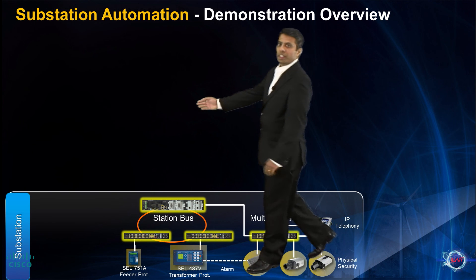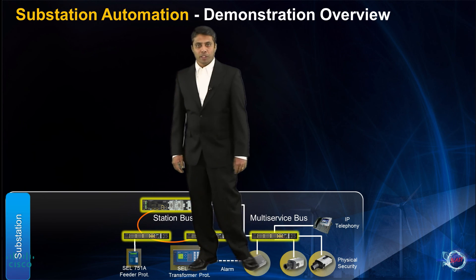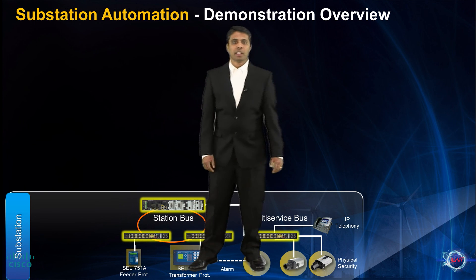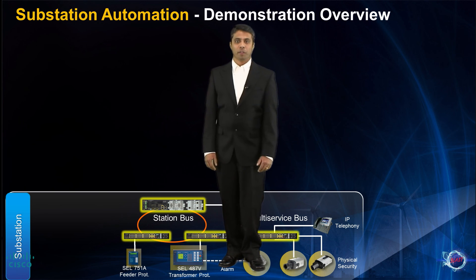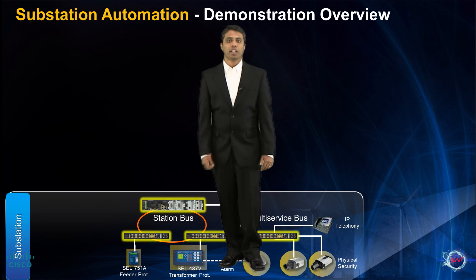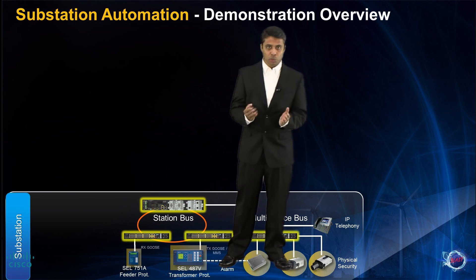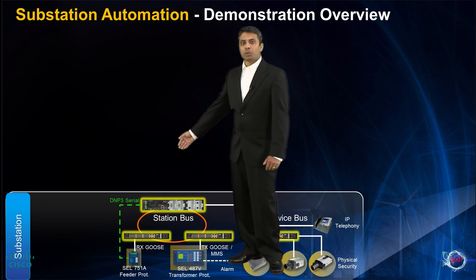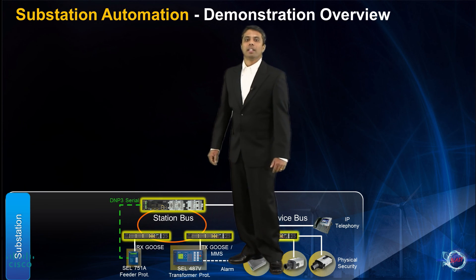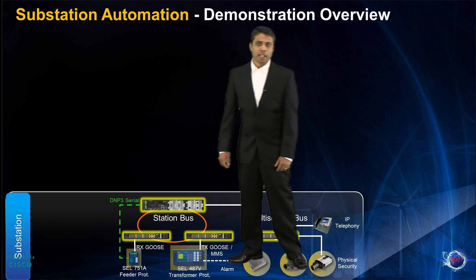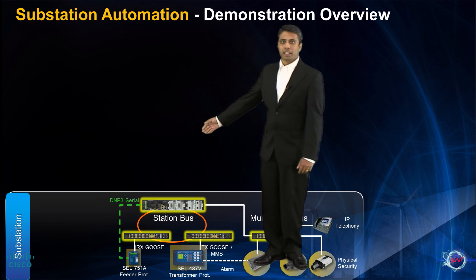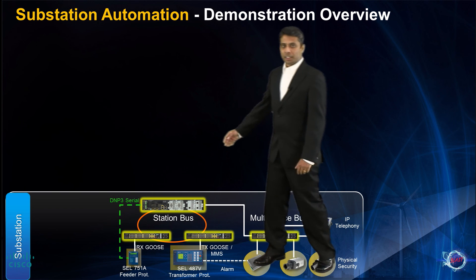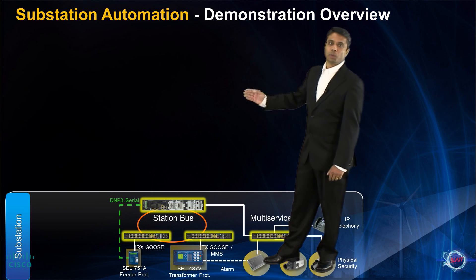The ring topology enables a high bandwidth gigabit ethernet fiber ring with fast convergence capabilities suitable for protection and control devices using IEC61850 protocols like GOOSE and MMS. Relays with legacy RS232 interfaces using DNP3 to communicate can be accommodated by connecting them directly to the connected grid router's serial ports and tunneling the raw serial data over the IP network.